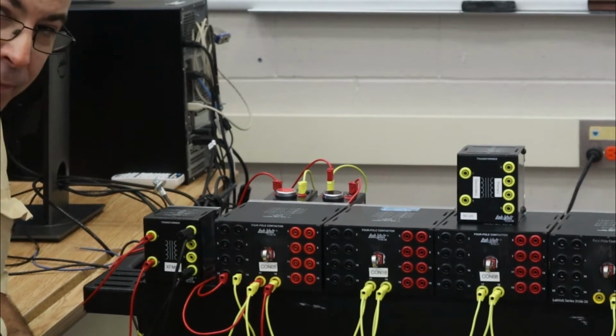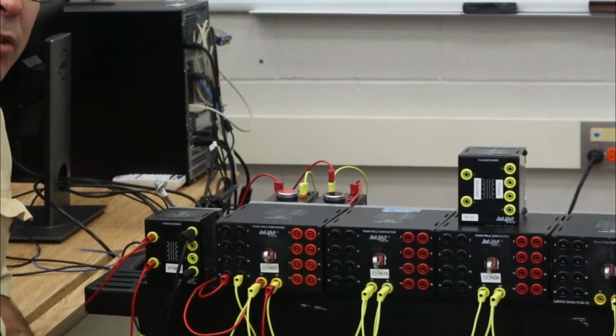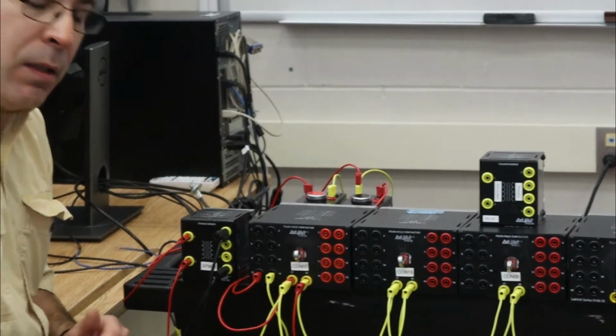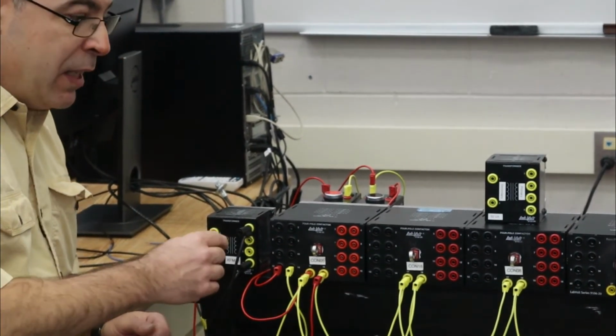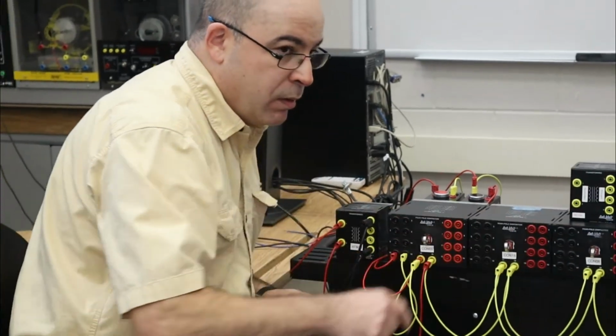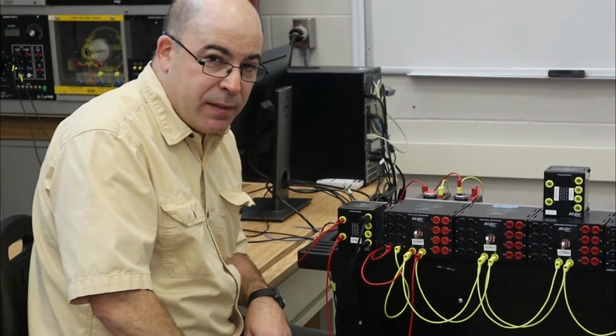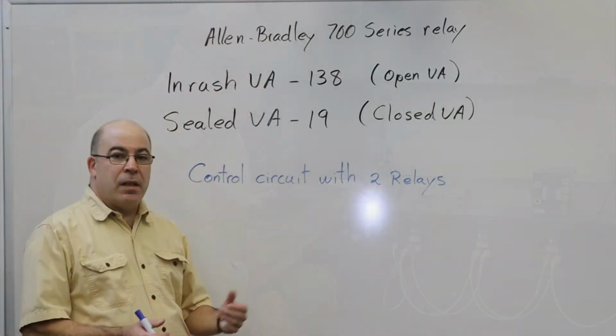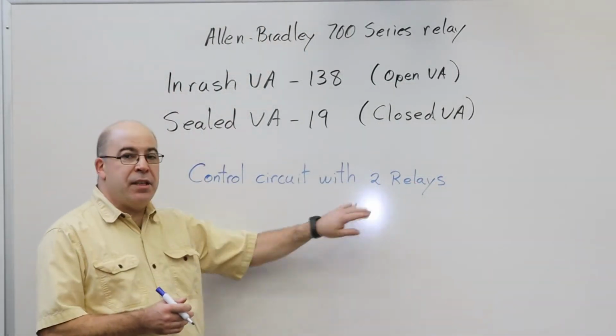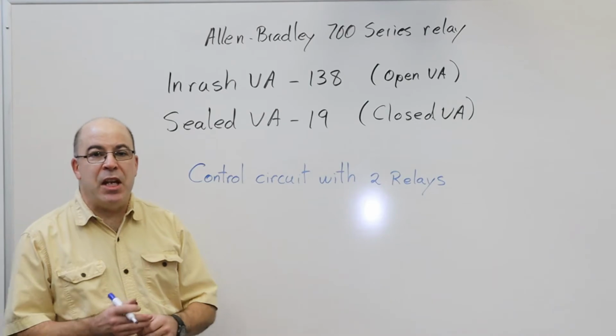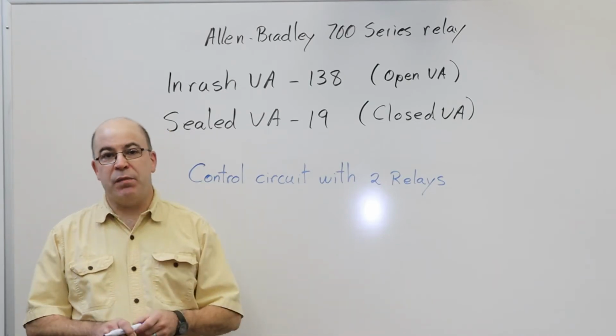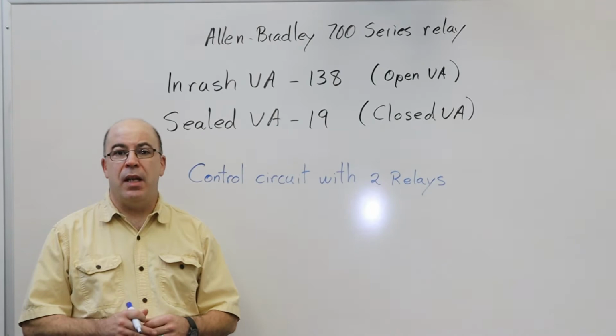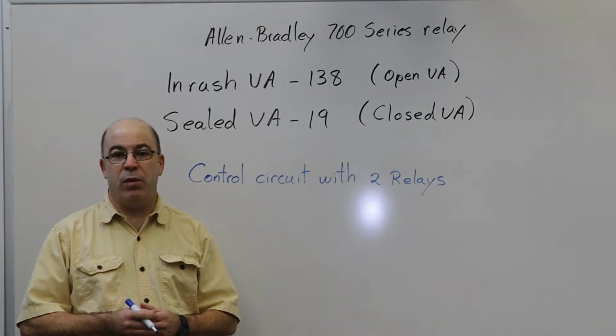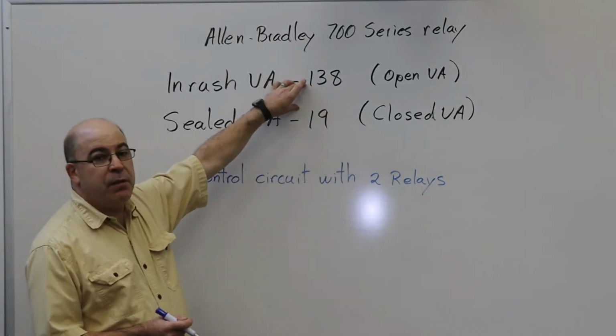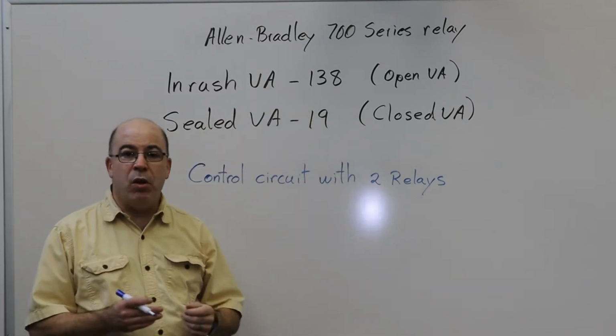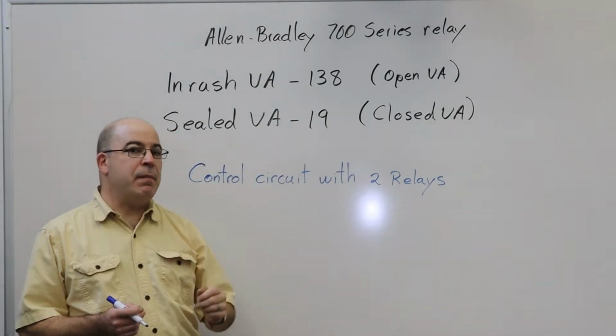How do we solve this? Well, the first thing is we actually have to go back and size the control transformer to allow for the amount of inrush power that is required by each of these devices. Now, how do we deal with a control circuit that contains two relays? I'm referencing information I obtained from Eaton as well as from Allen-Bradley or Rockwell Automation in how to properly size a control transformer. I need to take the values, the inrush VA, and I have to multiply it by the number of devices in my circuit.